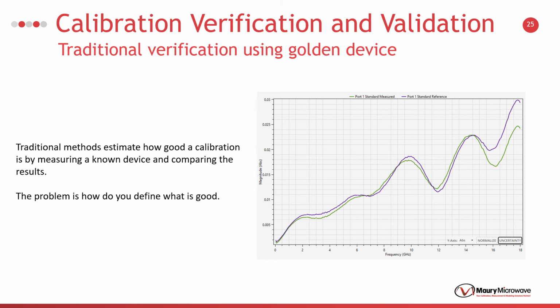For example, here we see two measurement data up to 18 GHz. Is this an acceptable calibration? Is it good in a particular frequency range? We can see that there are some small differences around 4, 10, and 12 GHz and a clear separation after 15 GHz. How can we decide to continue?